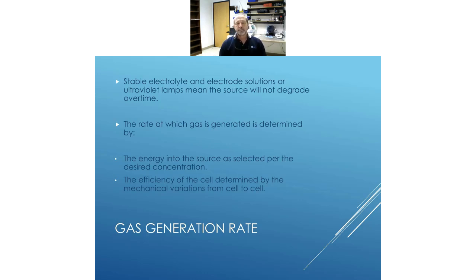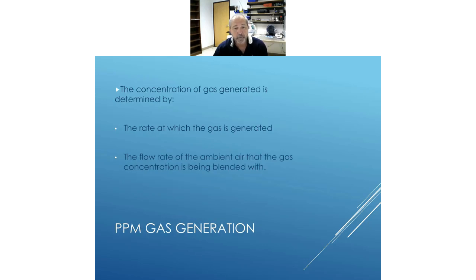If you were to buy a chlorine gas cylinder at 5 parts per million, that's what you get. With these generators, you can vary the flow rate, you can vary the output. So for different sensors that want different concentrations of gases, you can calibrate all different things with one generator.